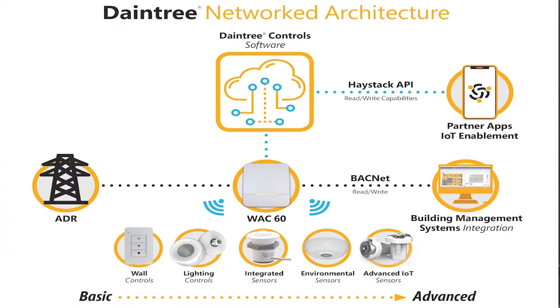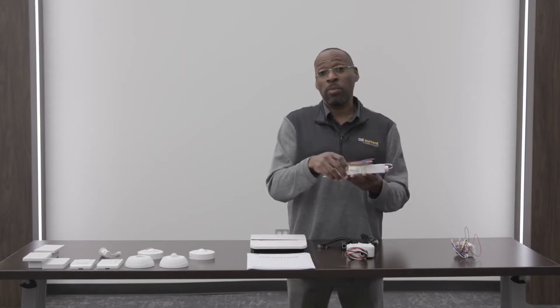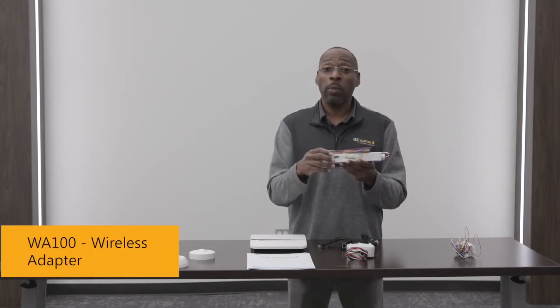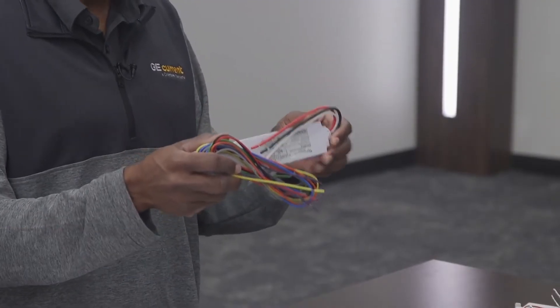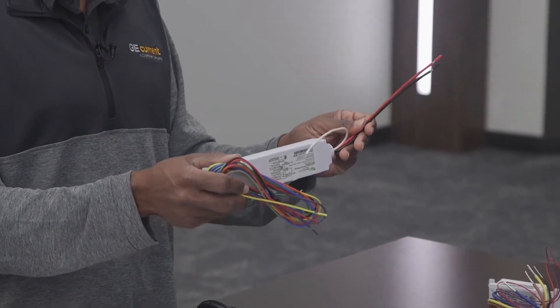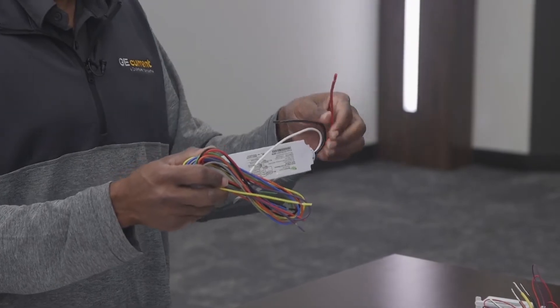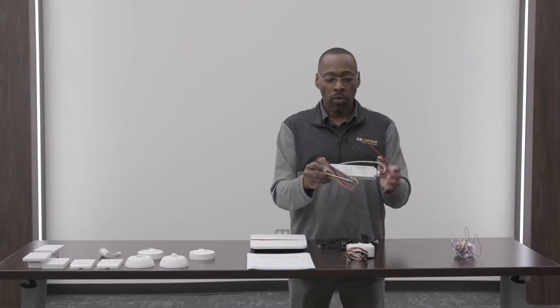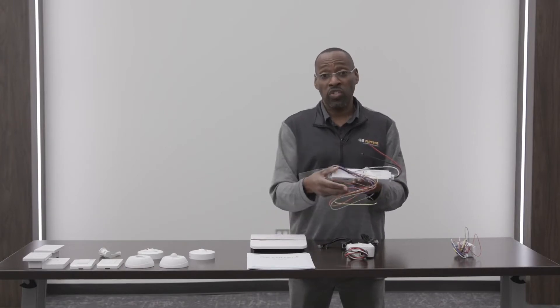Now I'm going to go through some of the wired devices we have within the system. This is where it really gets fun for a lot of the installers, because there are a lot of different dip switches and different things that may need to be set. This is our WA100 device — it is a lighting relay that turns lights on and off. You have to power up the device, and then there's a switch leg that goes out to different lights that are in sequence with the system to turn them on and off. This device does have a radio inside of it that again talks back to the WAC so we can control it.